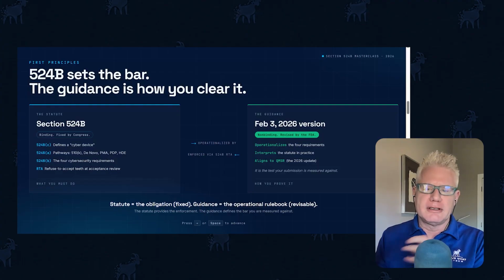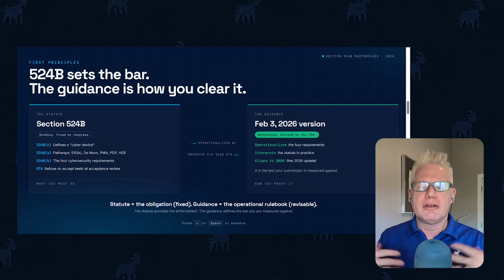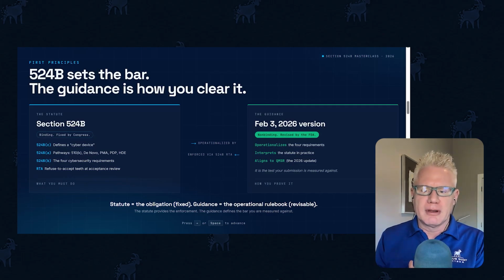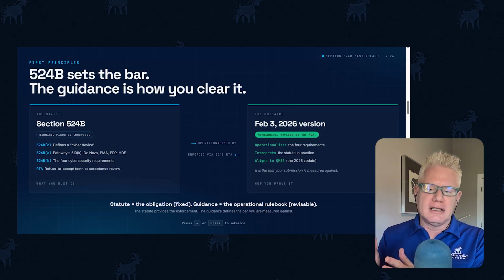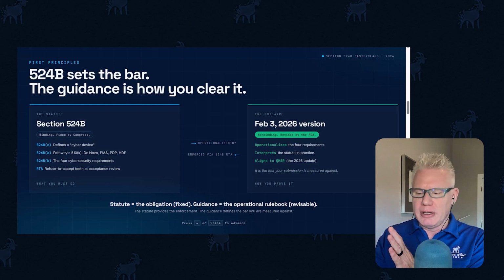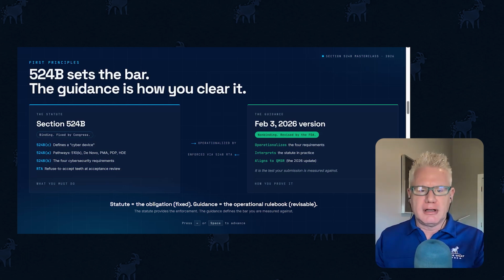So what the FDA guidance does, it operationalizes those 4 requirements. It interprets the statutes into practice, so you know what to follow, you know what to do. It's more specific, more prescriptive, and it aligns to QMSR, the Quality Management System Regulation as well. So now, cybersecurity equals quality, and it's part of a quality management system. So the statute is the obligation that doesn't change. The guidance is the operational rule book, and that can be revised later on. So how we operationalize the law or the statute can change as the FDA sees fit.